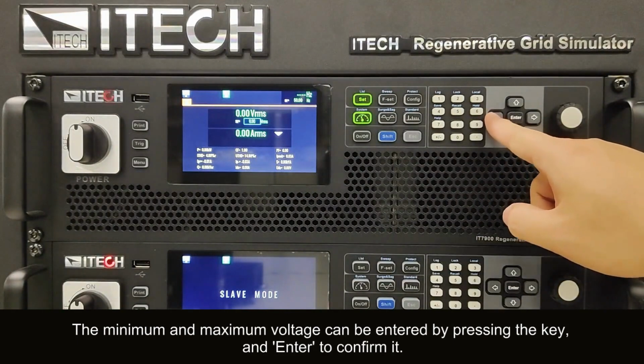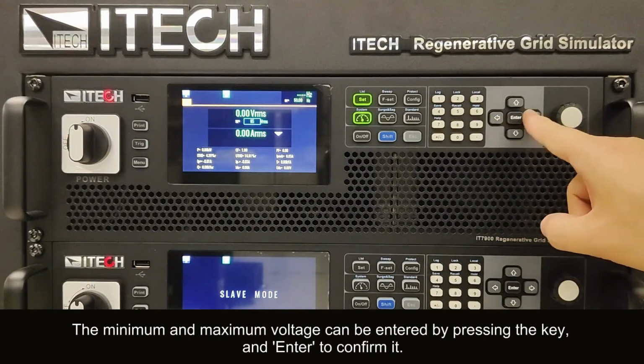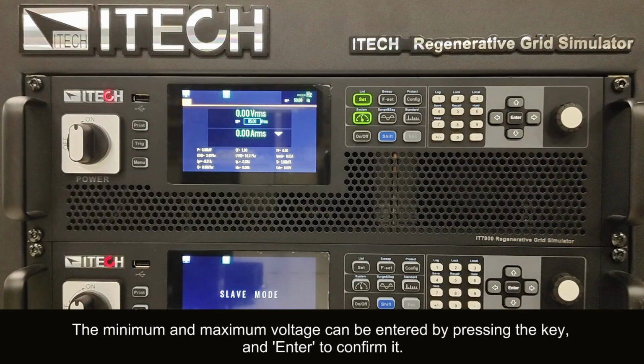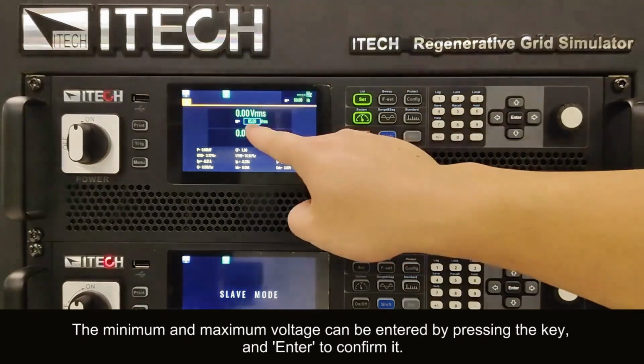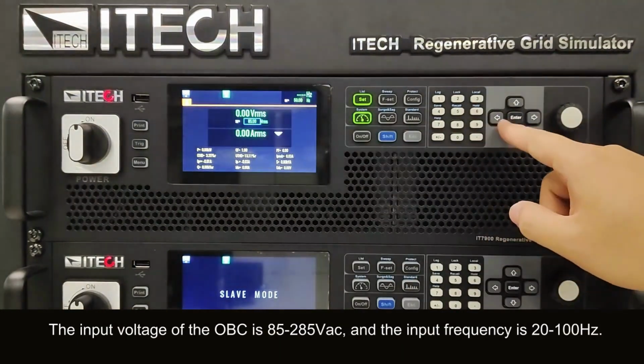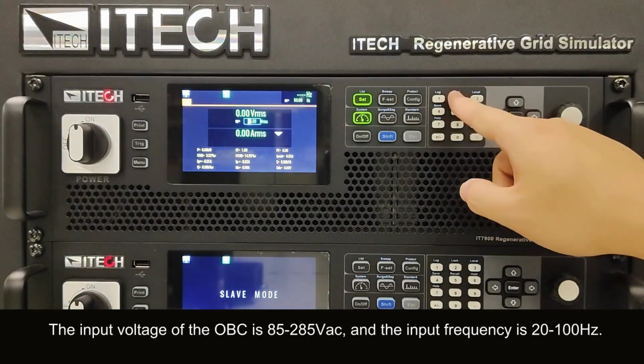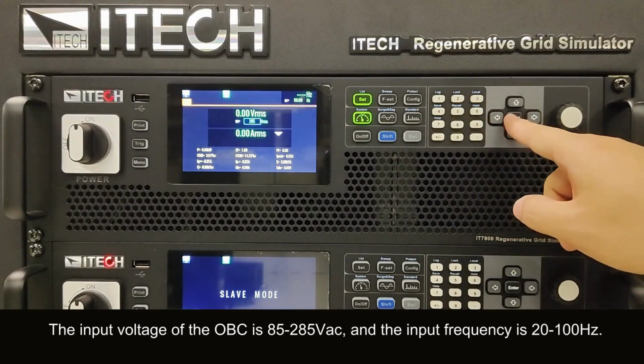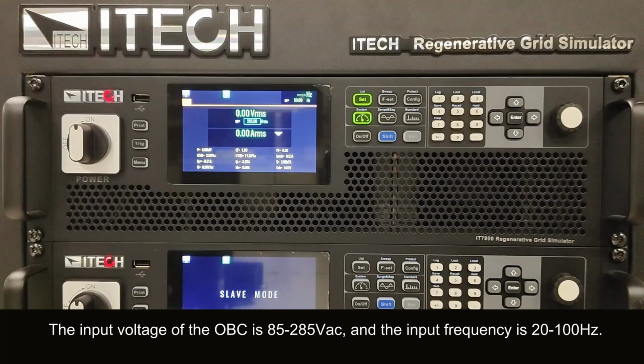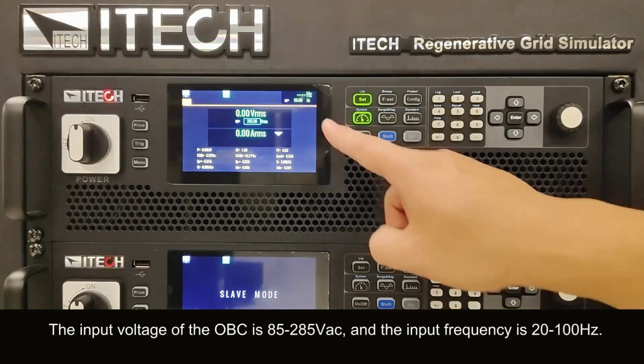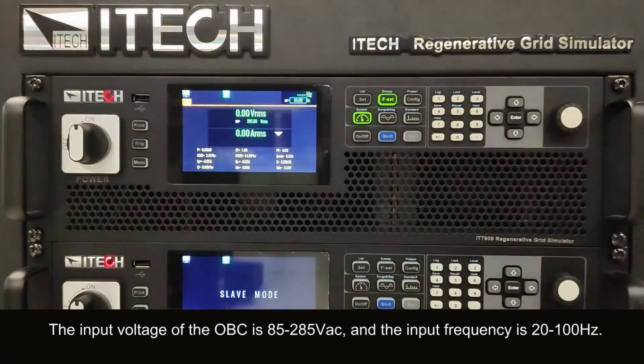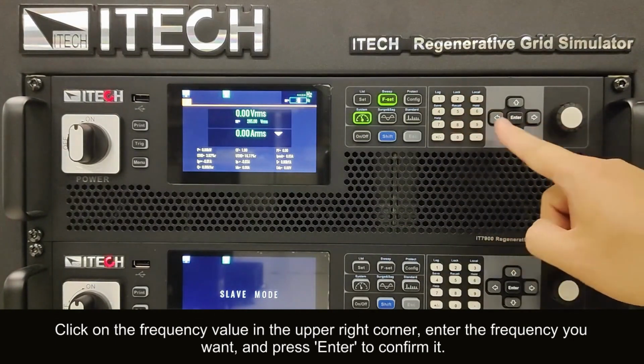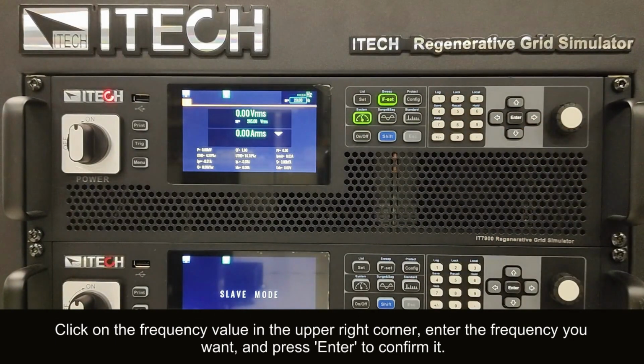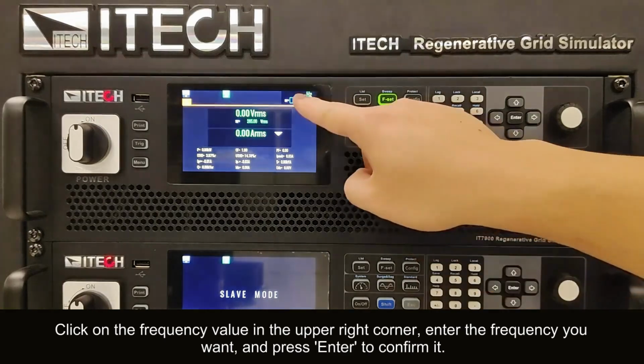The minimum and maximum voltage can be entered by pressing the key and enter to confirm it. The input voltage of the OBC is 85-285 VAC, and the input frequency is 20-100 Hz. Click on the frequency value in the upper right corner, enter the frequency you want, and press enter to confirm it.